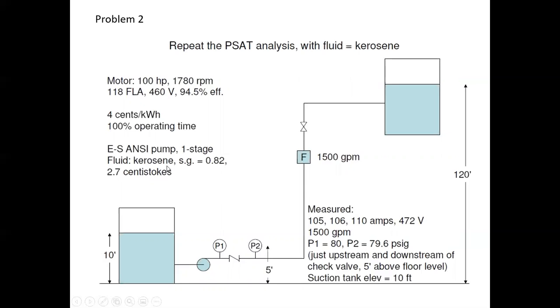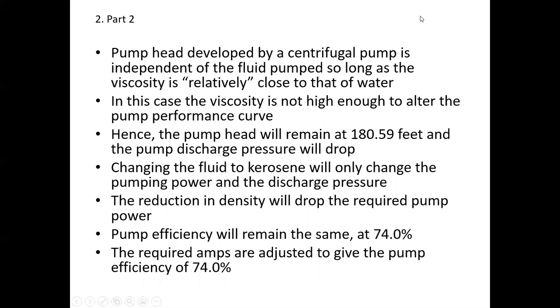So when you change it, you note that the specific gravity is 0.82 and the viscosity is 2.7 centistokes. So the viscosity is 2.7 times what it was before, and the specific gravity has been reduced by 18% from 1 to 0.82. The question is, what impact is this going to have on the pump? Well, this is some stuff we really haven't talked about, so this is a good opportunity. If you search the literature, you can find, and I have not mentioned this yet, that the pump head developed by a centrifugal pump, the pressure increase that the pump puts into the fluid, is independent of the fluid so long as the viscosity is relatively close to that of water. And of course, the question becomes, what is relatively close?